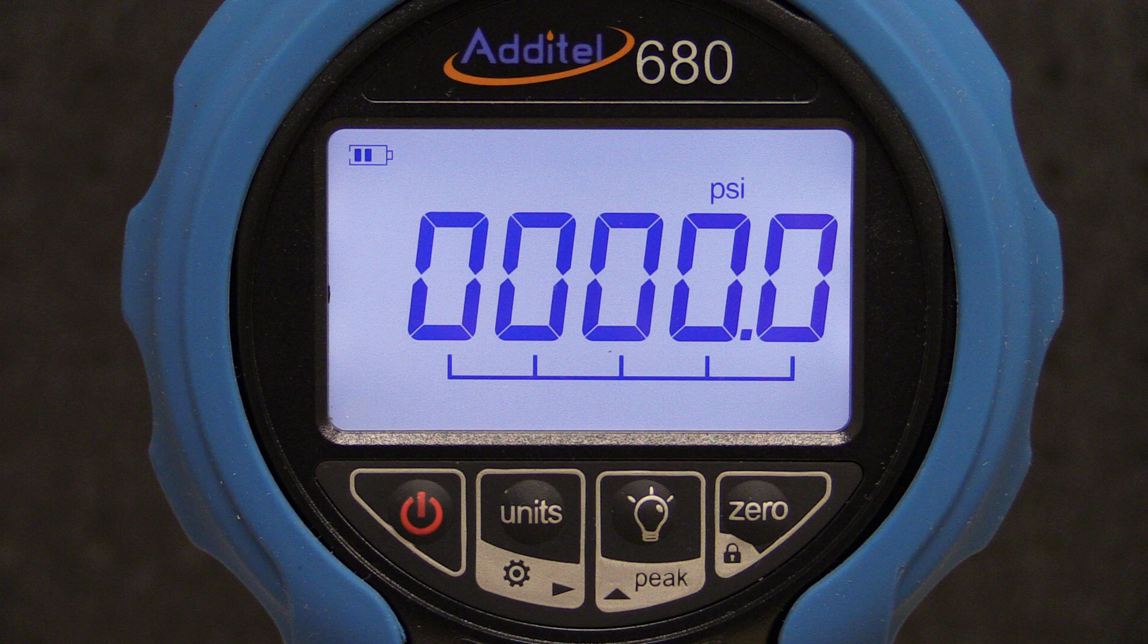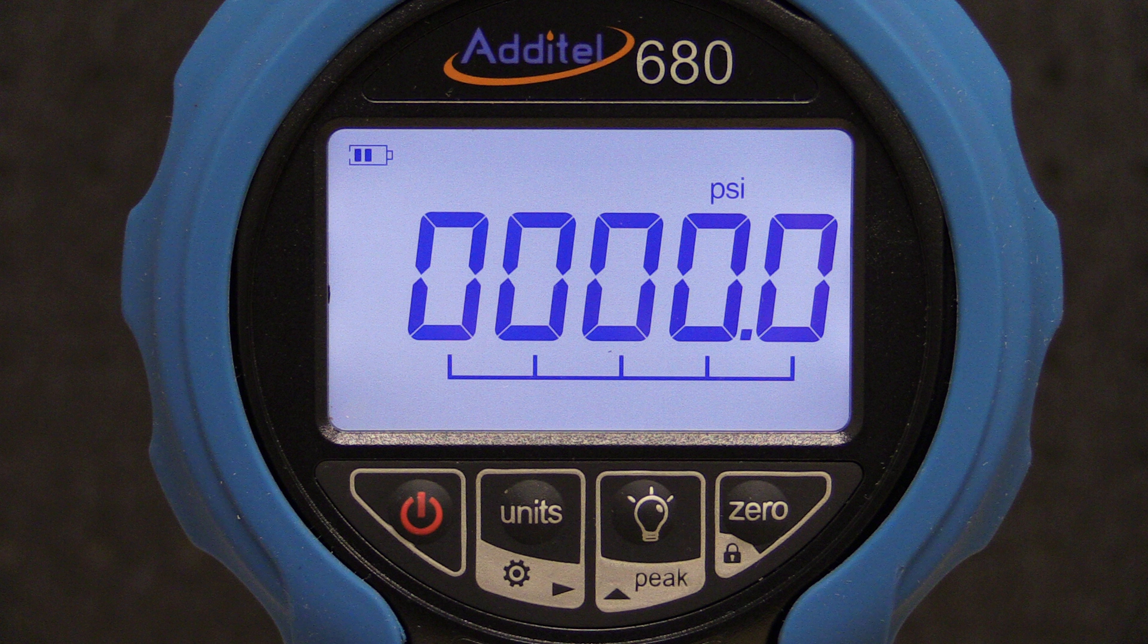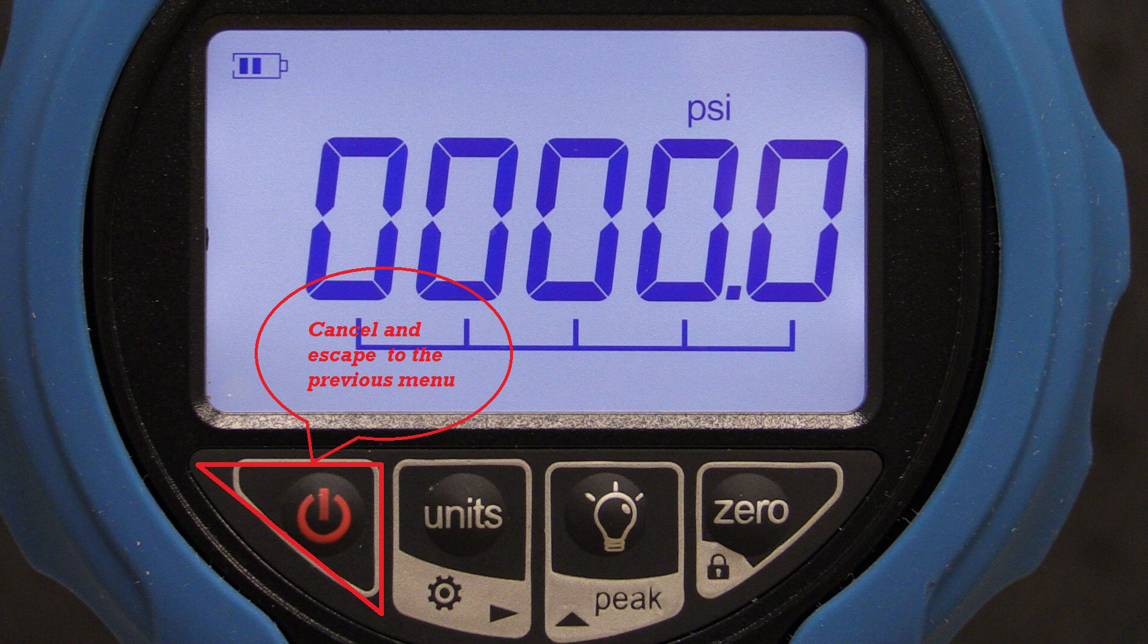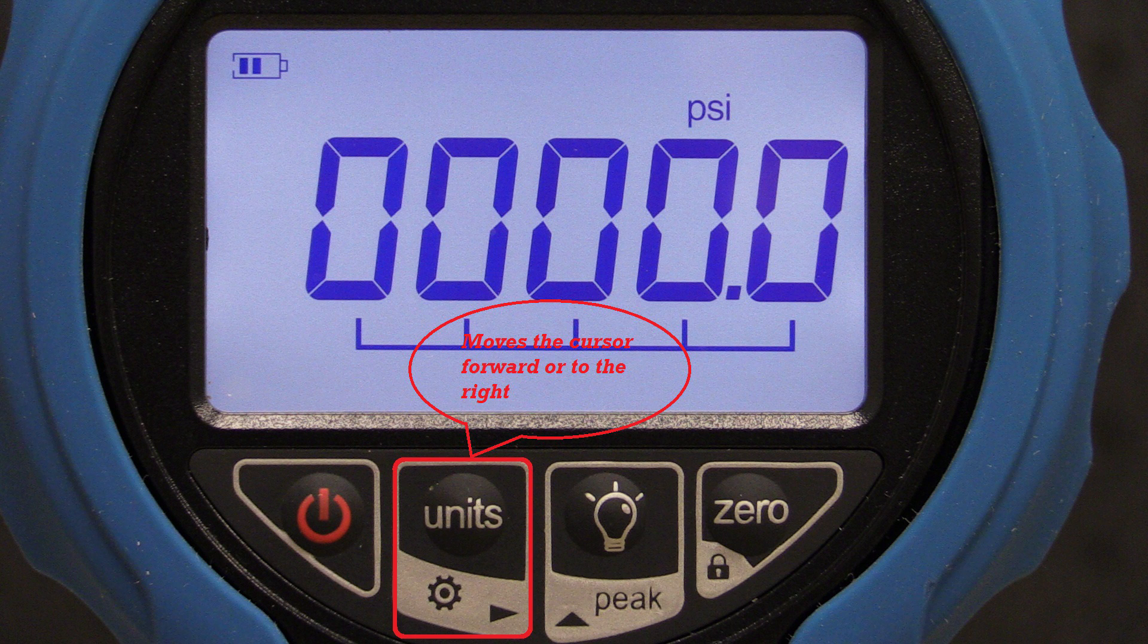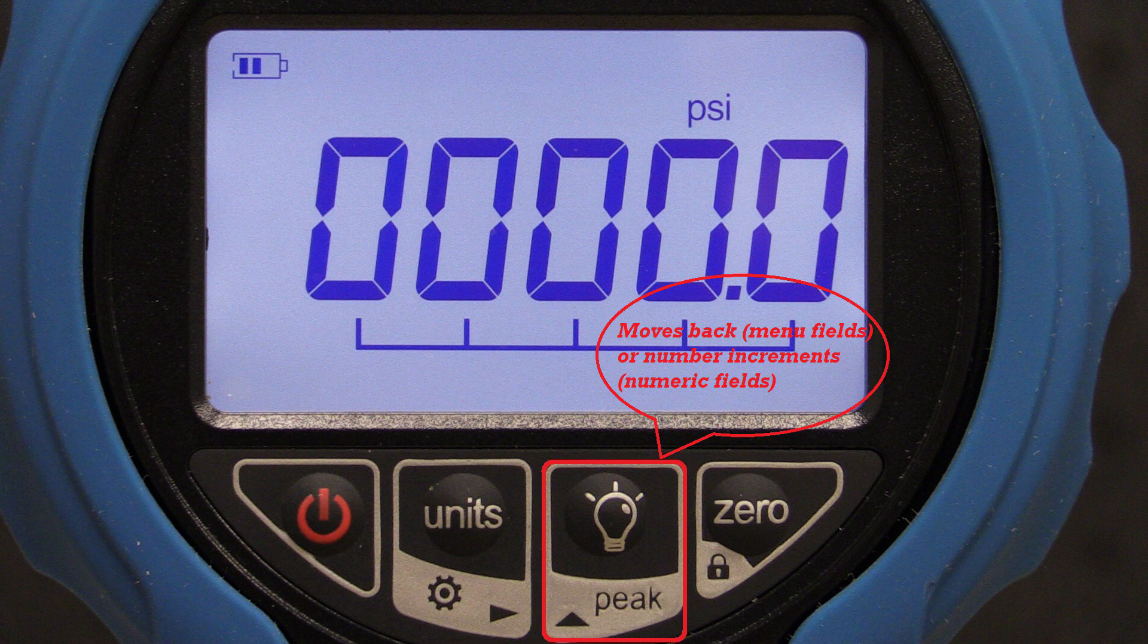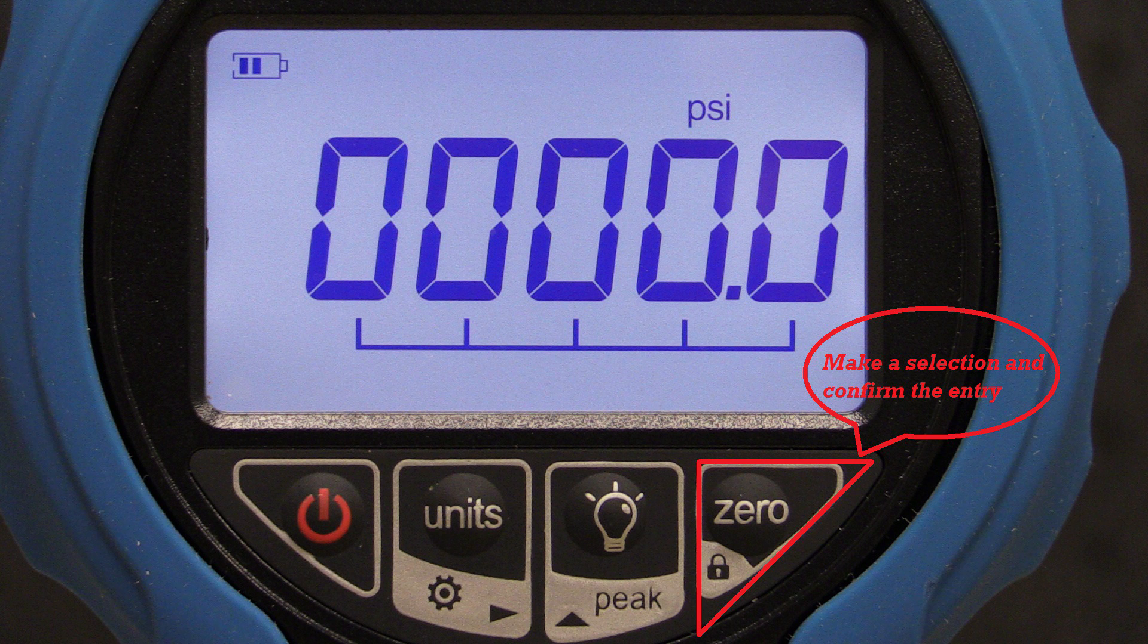In order to navigate the ADT-680W menus, it is helpful to understand the secondary functions for each key. When in the menu, the power key cancels and escapes to the previous menu. The units key will move the cursor forward or to the right. The backlight key will move the cursor backward when in the menu and number increment when editing a numeric field. The zero key is used to make a selection and confirm the entry.